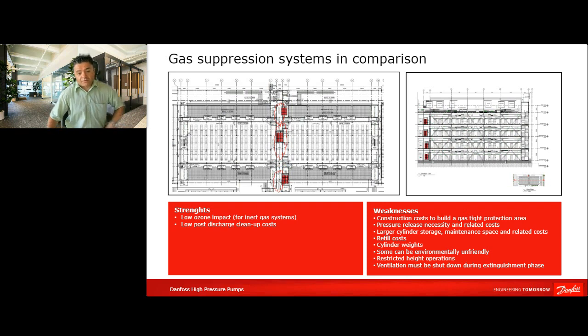The next one, which is also shown and demonstrated in these rooms, is the space that you have to consider for all those cylinders and cylinder racks. If you have, for example, a building which goes over many levels, you might have allocated rooms and spaces for each level, and these are spaces that you could have used for something different. So you could save money and use that for maybe additional server racks or some other applications. In a high-pressure water mist system, you have it possibly somewhere in the basement, and from there you connect this pump system through the pipes and then zone valves into different zones, and everything is localized in the basement. The spaces and dimensions that you consider for a high-pressure water mist pump system are by far smaller than for a gas extinguishing system.